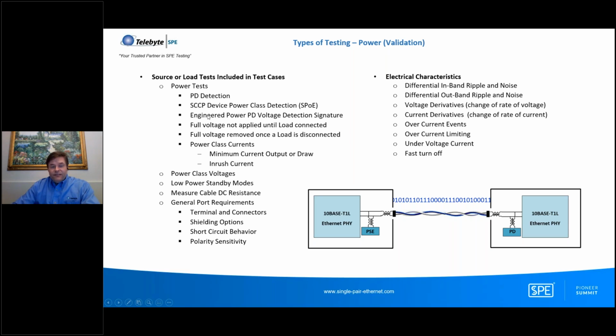Then in the advanced physical layer, they have what they call engineered power. So it's already predetermined by the design of the network what the power class will be and what the power delivery will be. It's hard-coded, hardwired, or the device can only deliver what it's going to deliver. It does have to find out, though, if the PD is on the cable or not. So there is a voltage detection signature that is used to turn the power on when the device is connected to the link. So we want to make sure that full voltage isn't applied until you have the power device load connected. And then once the power device is removed, voltage should turn off.